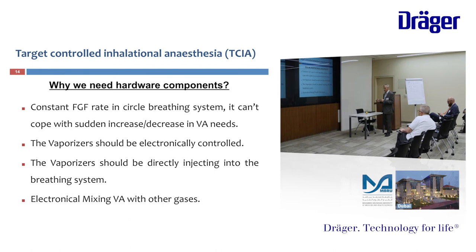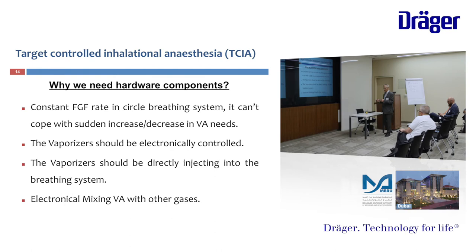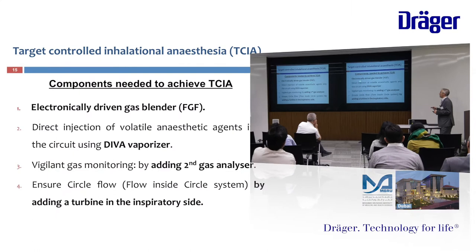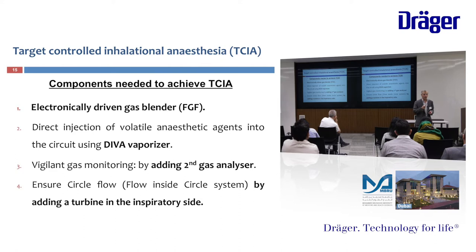And finally, electronical mixing of volatile anesthetic with other gases. Components needed to achieve TCIA: electronically driven gas blender, direct injector for volatile anesthetic — the DIVA vaporizer — and we need to monitor very accurately and very closely the gas. Because of this, while using the automatic gas control, we need to have a second gas analyzer. We don't depend on one gas analyzer because we will reach very critical levels of fresh gas flow.